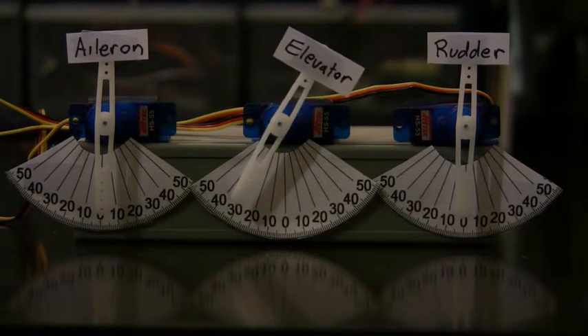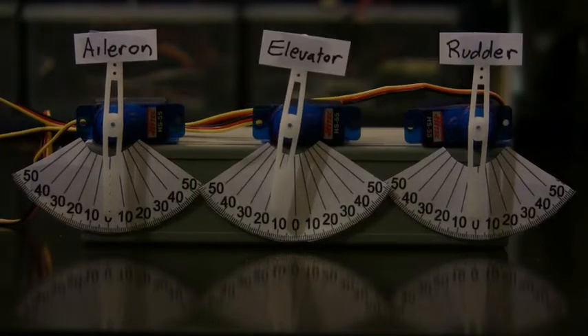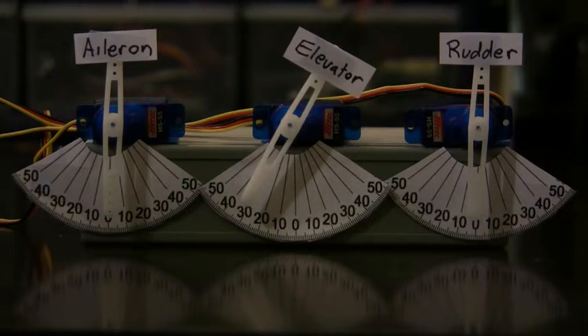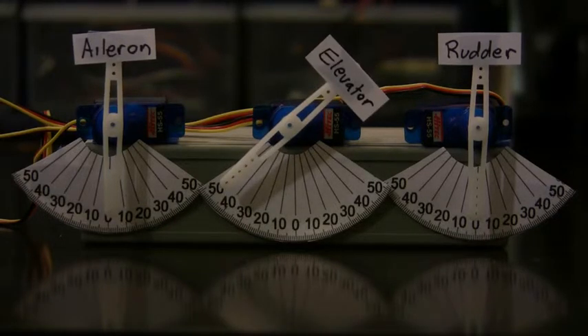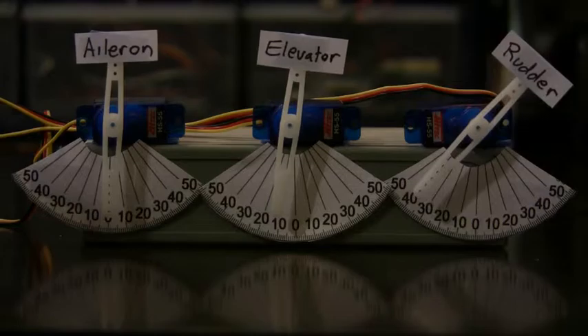It goes through it in about a minute roughly, and once it's done, all servos go back to neutral and the system can be turned to reset to disable it. So if during this automatic servo motion sequence you want to stop, you can pause briefly by going into manual mode, and then it'll go just to that next sequence and then stop there waiting for input, and then you can step through all the subsequent cycles using that manual advance switch.